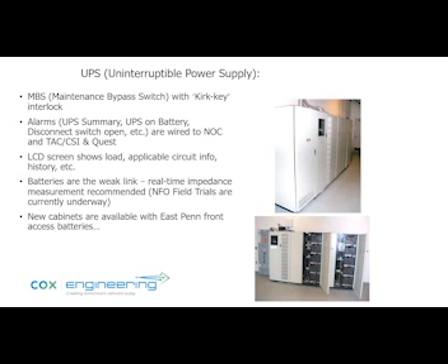These batteries are more like Group 31 size, similar to power supply batteries or car batteries, etc. They're not like telecom batteries. Telecom batteries are slow rate batteries; these are high rate batteries, typically used because a UPS might run for maybe 10, 15 minutes, sometimes a half hour. So they're built to take a high load very quickly - think of it like a sprint, or being pummeled in a boxing ring. That's what happens with these batteries, and that's why their lifetime isn't that long, maybe 2, 4, 5 years. They're just a different application, different design, with thinner plates - they're called high rate batteries. Telecom batteries, which last 3, 4, 8 hours, have thicker plates and are more like a long, slow distance run. It's just a different application, so the chemistry and composition of the batteries is a bit different.